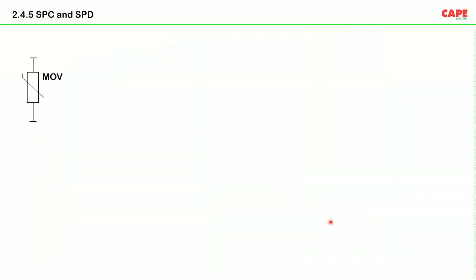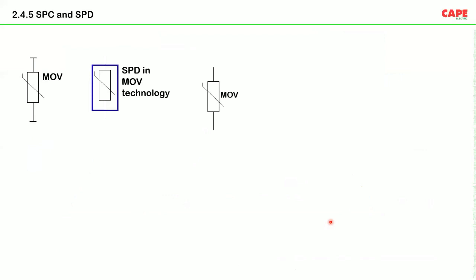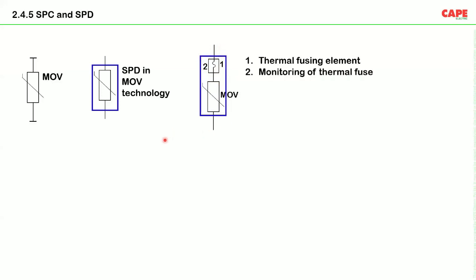So each of these devices has its advantages and disadvantages. Now you are seeing an MOV. If you look at the symbol of an MOV, you will see an MOV in a box. What it means is that inside the box, there are some protective devices, 1 and 2. Not only an MOV, there are some protective devices integrated into it. Then only this combination can be called an SPD. SPD is not just an MOV. SPD is an MOV plus its protective devices. Number one, the thermal fusing element and the monitoring of the thermal fuse. That is what is written in 1 and 2.